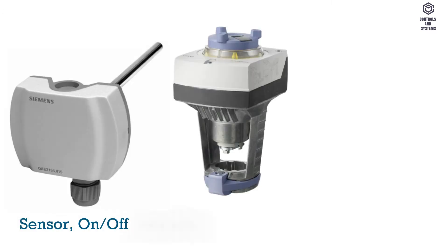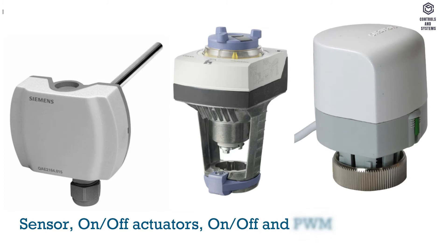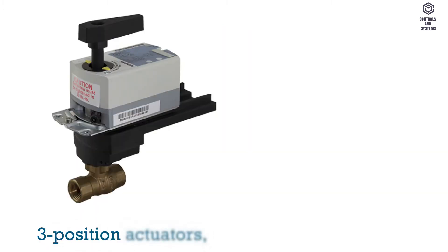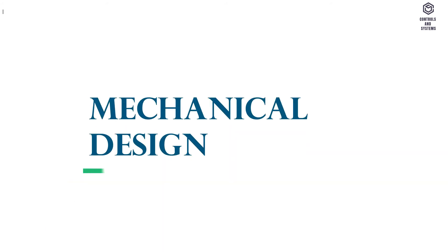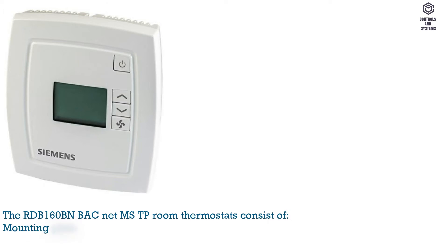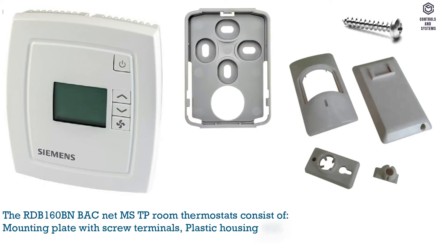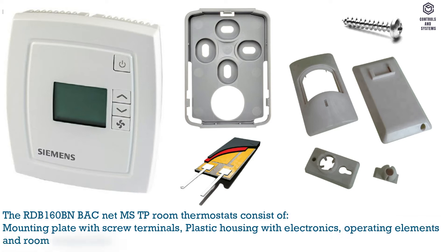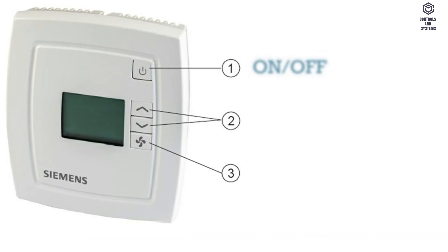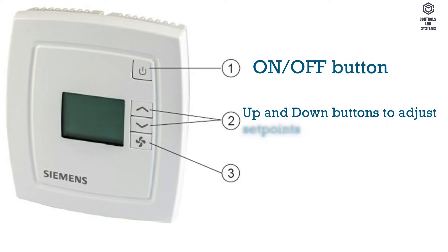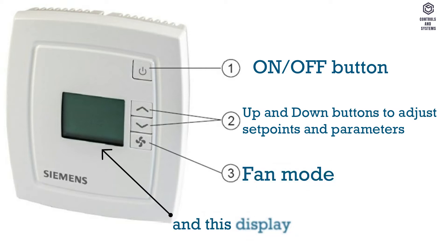Equipment combinations include: sensor, on/off actuators, on/off PWM actuators, three-position actuators, and DC 0–10 V actuators. Mechanical design: the RDB 160BN BACnet MS/TP room thermostats consist of a mounting plate with screw terminals, plastic housing with electronics, operating elements, and a room temperature sensor. Operation: the display is operated using the buttons on the controller — (1) on/off button, (2) up and down buttons to adjust set points and parameters, (3) fan mode button. The display has a backlight LCD.